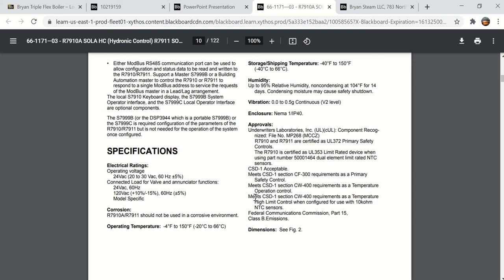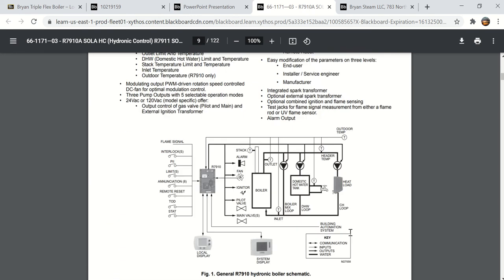And right here in particular, you see where it says that it meets section CW400 requirements as a temperature high limit control when configured for use with a 10K NTC sensor. So when I was talking about the 3-wire sensor meeting a certain code, that's what it is, and that's the section in the CSD1 code that requires you to have that type of sensor for high limit control. It's been approved for that kind of application.